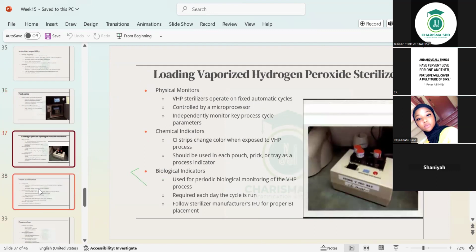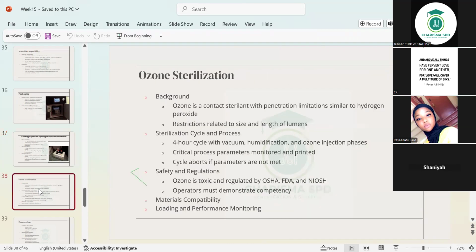The loading is also the same thing. We've got to have the physical monitors and the chemical indicators and the biological indicators. You have to make use of them. There's nothing like a load being sterilized without any physical, chemical, or biological indicator. That is the only way you can measure your sterility. That's the only way you can measure the performance of the sterilizer. So there is no way you're going to go through a sterilization process without these chemical indicators or biological or physical monitors. Okay? So that's just a revision.